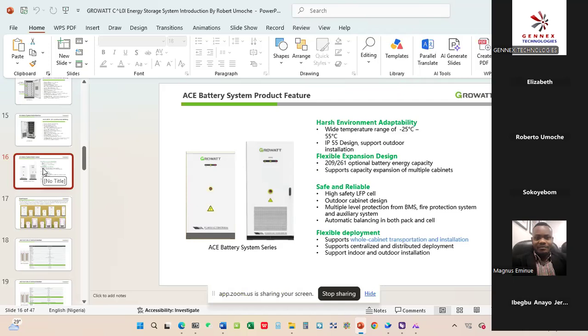These systems have the ability to export and import power. Importing power means taking power out of the grid to charge your battery or supply the load. Exporting means taking power from the PV and sending it to the grid. In some advanced countries you can use this as another source of income, producing more than what you need and exporting the excess to the grid while getting paid. Even in Kenya they do it, sending excess power to the grid. So these are the unique features we have for our system.